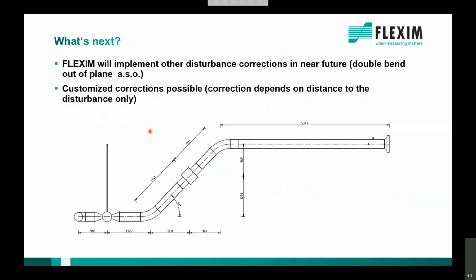So what's also possible, here is an example of a special solution we did for a customer here in Europe. It's a gas customer here at the dosing station, and he always has the same piping for all the dosing stations, and he wanted to have the best accurate reading. So what we just did was testing it on one single pipe and defined the correction factors. And then we had the correction factor for all other pipe sizes as well, because the correction factor we defined is independent of the Reynolds number. That means as well it is independent on the pipe size and independent of the flow velocity.